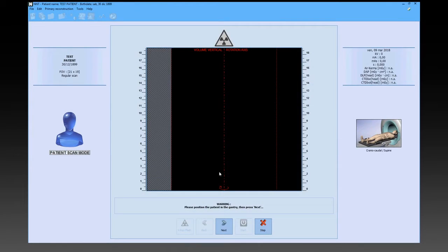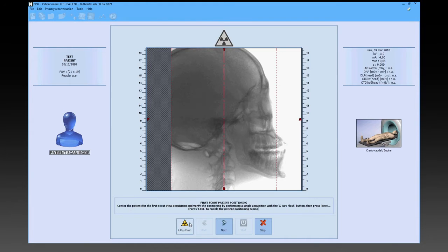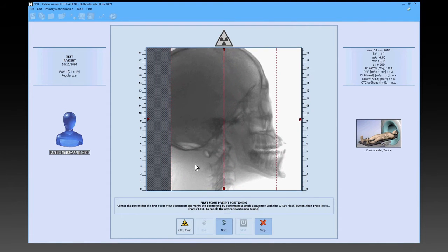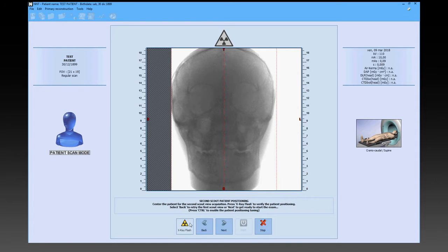After going back to the console, the physician hits Next and using the X-ray flash button obtains the first scout image. The scout image will then be displayed on the screen, allowing the patient's position to be adjusted by holding down the control key and moving the image with the mouse. After completing any required adjustments, a new automatic scout image will be obtained to be checked.